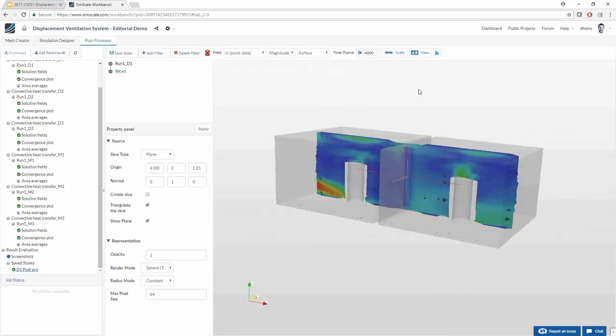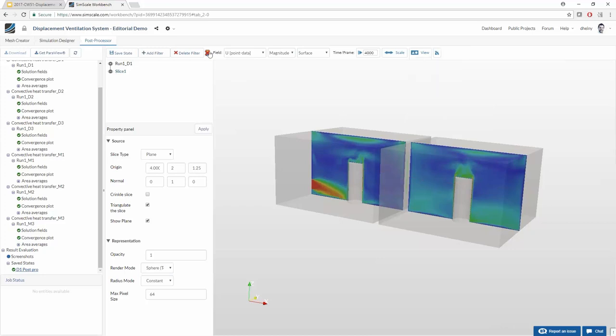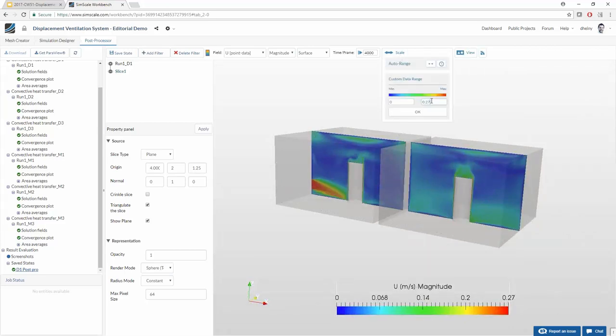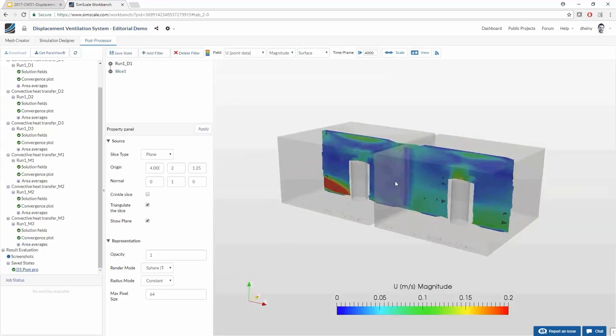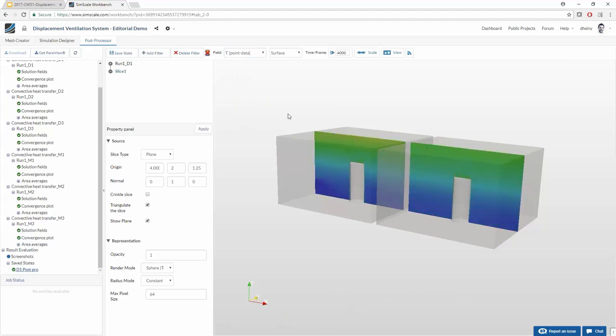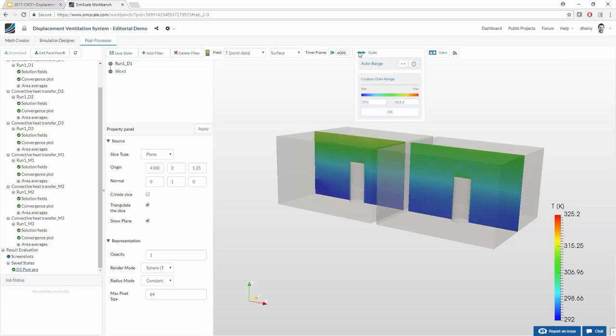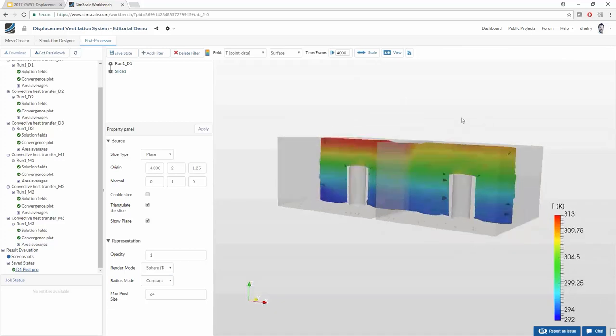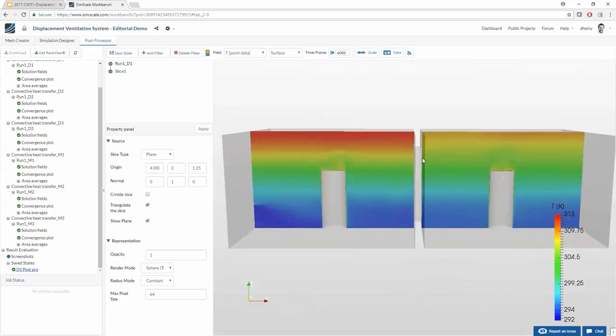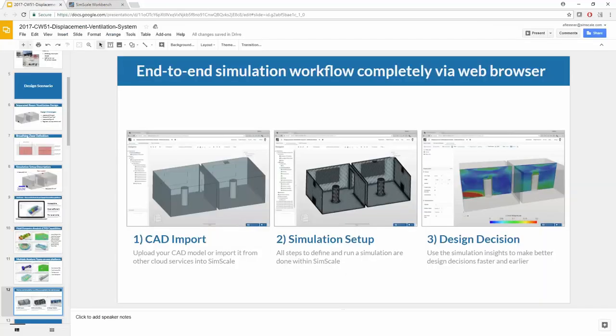Once the simulation is computed, I can directly visualize results online. What we're looking at here is the velocity field in a cut section through the room — about 0.2 meters per second shown in red. I can also switch this over to temperature to see the temperature distribution. And here I can already see the stratification of temperature — the different layers — and how hot it gets in the room. This is really the full workflow: bring in your CAD model, generate the mesh, set up the physics, run in the cloud, and post-process online.